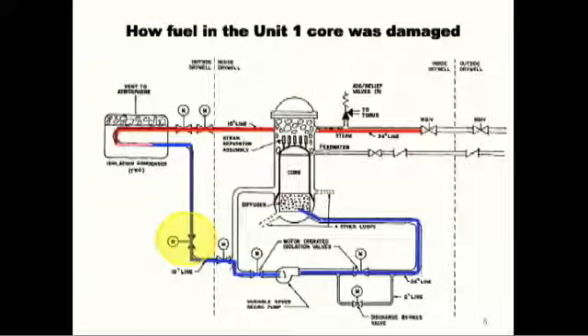There was no steam leaving, it was all being reused, so the amount of water in the reactor vessel was remaining the same. The operators about 11 minutes later turned that system off. As at Three Mile Island, you turn off emergency safety systems, you're basically toying with the devil and the devil wins. But they turned the safety system off, they closed that valve 11 minutes after it opened, because the temperature of the water inside the reactor vessel was cooling down at 300 degrees an hour.